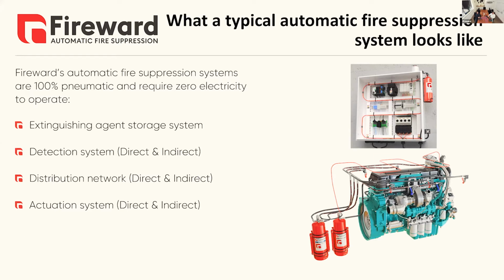So if we crack on with the following slide, really try and give you an idea of what a system actually looks like. We've got a couple of images on the side here. The Fireward system is completely autonomous and it's 100% pneumatic. So this is controlled through the proprietary detection tube that we have here. So it doesn't require any electricity to operate, which obviously gives you lots of peace of mind. And regardless of the status of the machine it's protecting, it has its own capabilities built in. So in all the examples, you have an extinguishing agent storage system, basically a posh word for a cylinder, which contains the extinguishing agent.